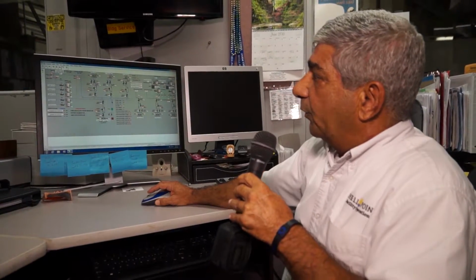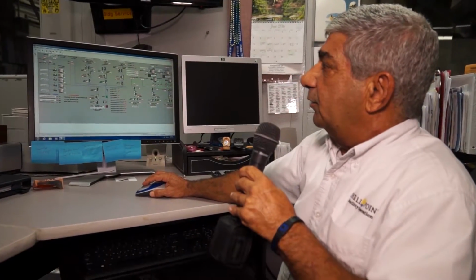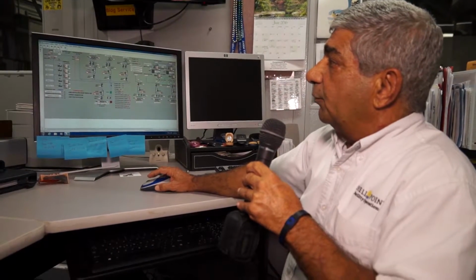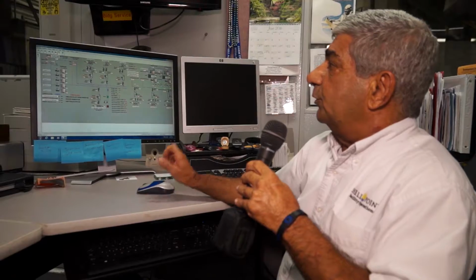Right now we're leaving the plant at 43.9 degree water, and we're coming back at 49.6. We're roughly pumping about 6,800 gallons of water through the system, which consists of about 5 miles of underground pipe from this plant to the furthest point at the turbine.